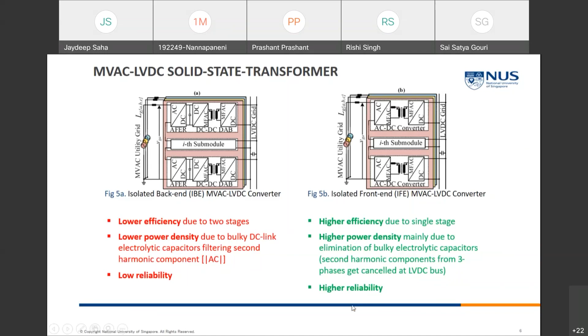Now, if you come to the isolated front-end topology, this is a single-stage topology, so you can have higher efficiency, and the second harmonic ripple is completely transferred to the LVDC grid, right? The three phases would similarly have their ripples transferred to the LVDC grid, but the three phases are mutually 120 degrees phase shifted. So when the second harmonic ripples add up, they inherently get cancelled. Automatically they get cancelled, and thus you do not need an extra bulky filter over there. So you can have higher power density and higher reliability.